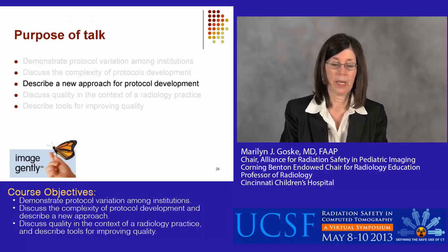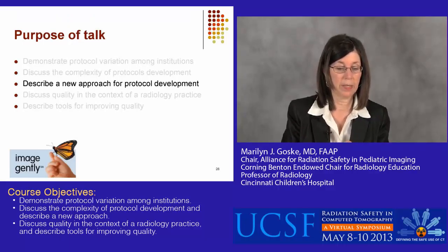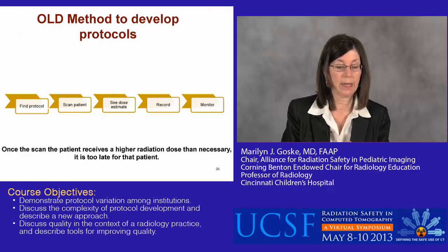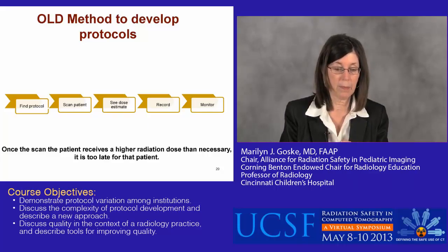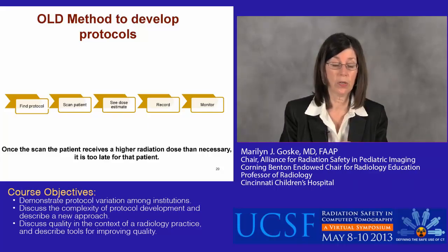Next slide. Now we're going to talk about a new approach for protocol development. And on this next slide, you can see that in the past, what we would do is start by having a protocol. We would then scan the patient, and we'd see what the dose estimate was in CTDIvol.